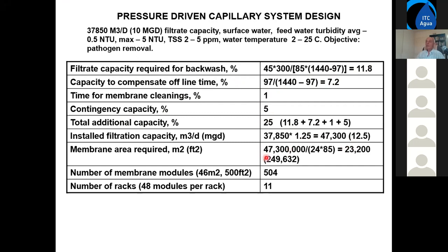So now we divide this by the membrane area to see how much membrane is required. This is the membrane area divided by 46 per membrane module. So we need 504 elements. If we have 48 modules per rack, we'll have 11 racks.